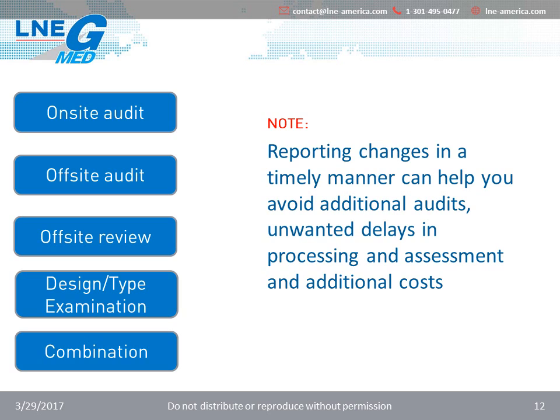Assessment of change by your notified body can vary depending on the type of change, your device classification, and the regulatory requirements. It can take one or a combination of the following actions: an on-site audit, an off-site audit, an off-site review, a design or type examination, and as I said, it can be a combination of more than one of the above.